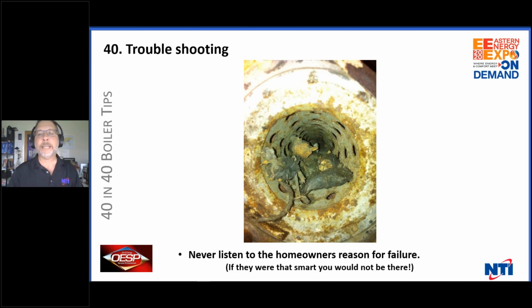Troubleshoot correctly. This one came to me because they had gone through 3 flame sensors and 3 igniters, and I got a phone call saying, I must have had a whole batch of bad ones. Do I have any more? And I said, that's not the problem. I said, pull the burner door and let's see what's inside the burner. I got nothing. I said, call me later. He didn't call me. He texted me this picture. That's a bat inside of a burner that was preventing it from firing. Please do your troubleshooting correctly and don't guess about anything.